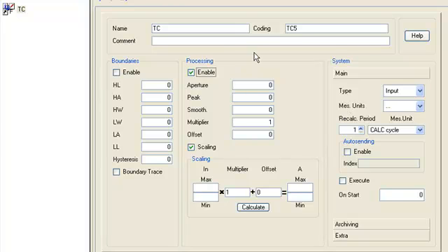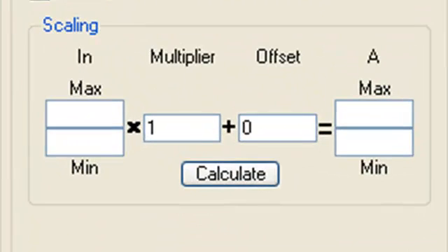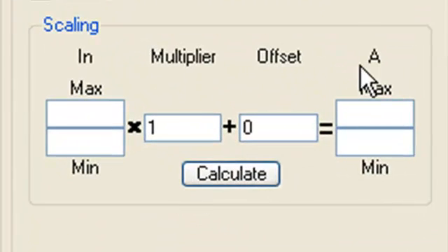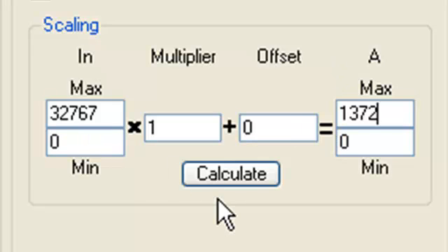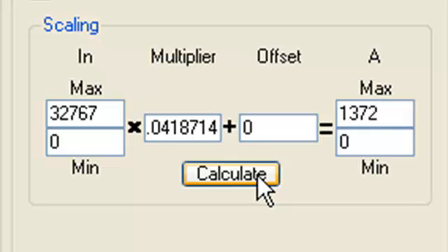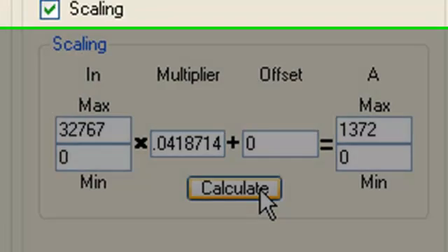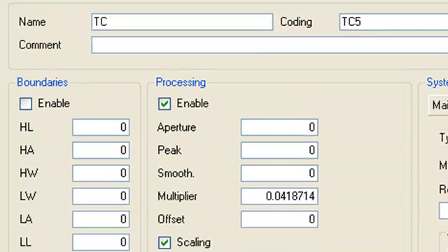In the subsection scaling, let's set the correspondence between ADC's code range and the temperature range. Press the button calculate and look how values for the multiplier and for the offset will fill automatically. Let's adjust recalculation period for this channel as one minute.